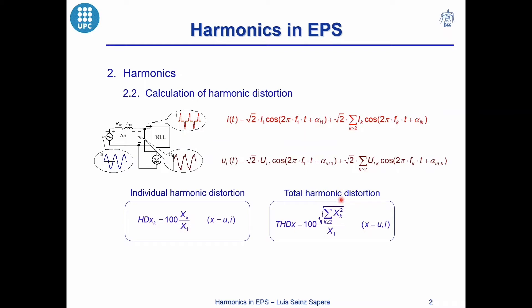The total harmonic distortion is a global ratio about the waveform pollution, and it is determined as the ratio between the square root of the sum of the squares of all the harmonics and the root mean square value of the fundamental waveform. These two ratios can be applied to characterize the distortion of both currents and voltages.